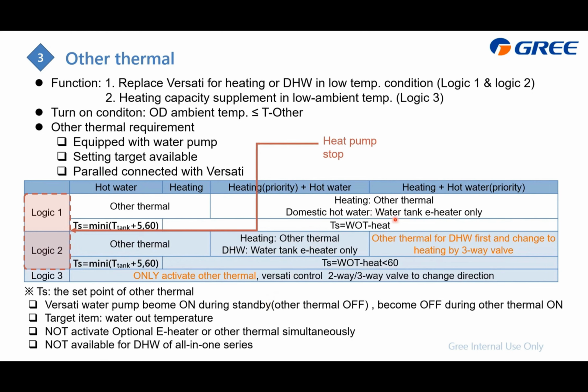Logic 1 is only heating up by the domestic water tank heater, and logic 2 is just like this. It will heat up the DHW first and then change to the heating by three-way valve if you apply the hot water priority first.